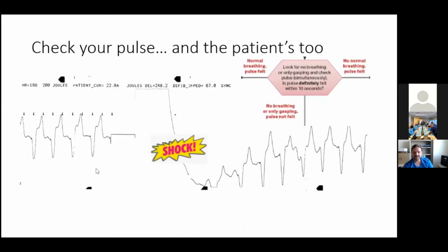You can see that what was happening was the patient was actually double counting. The defibrillator connected to the patient was counting the T waves and the QRS complexes, giving him a heart rate of 188, when really his heart rate was 94. He unfortunately was shocked for this.